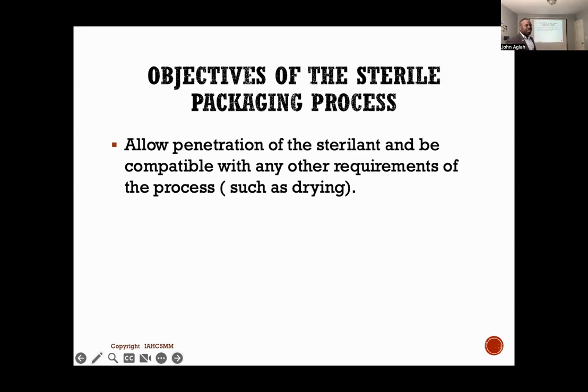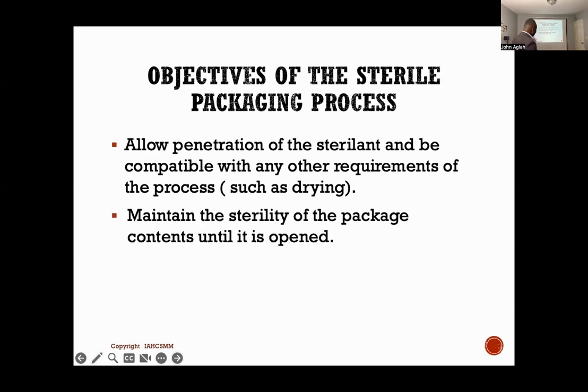So what this statement pretty much means is that in selecting the packaging for sterilization or for your instrumentation, the package must allow penetration. It must allow the sterilant to be able to go through it. If it is a metal container, if it is blue wrap or peel pouch, whatever sterilant you're using must be able to go through that. Okay. Maintain the sterility of the package contents until it is open.